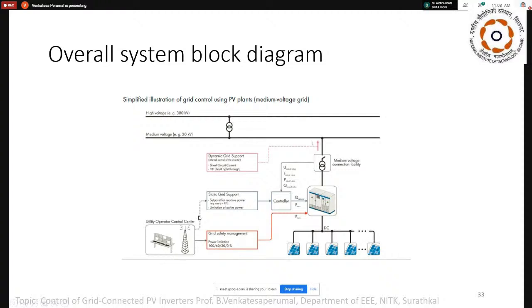The utility operator can give the information to the controller setting, that is P and Q. Till today in India, none of the inverters are supporting the Q requirement. Basically, all the power generation is a fixed P, and there may be a Q, but the Q value will be very, very low. It is set according to the site condition and is not extensively varied with conditions. Then, with the step-up transformer, it goes to the grid. This is the normal system when it is used.